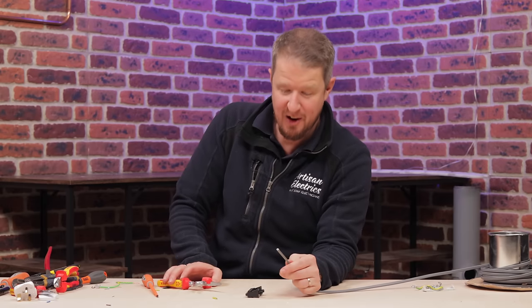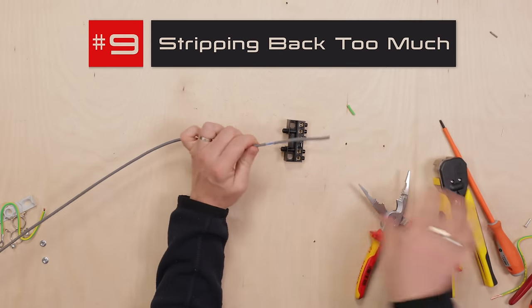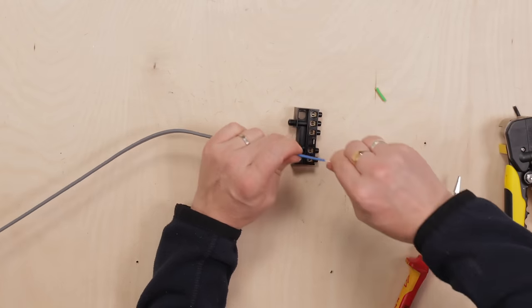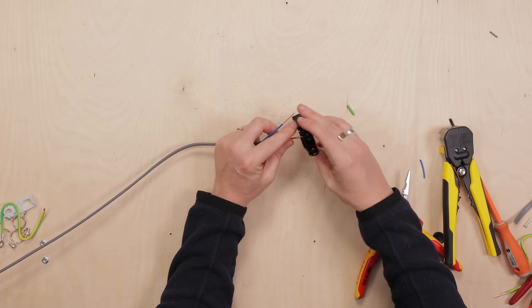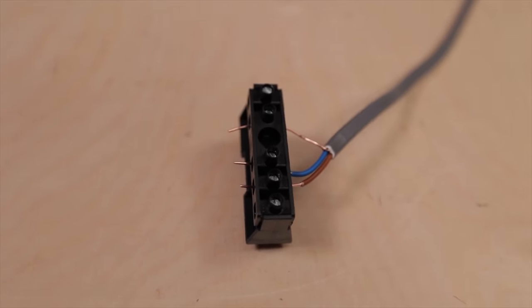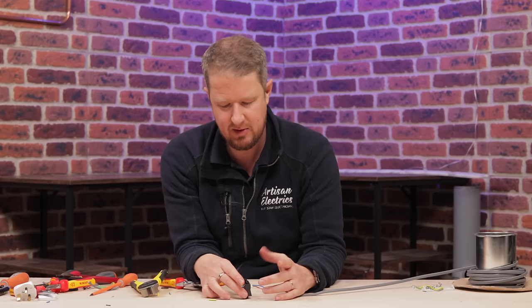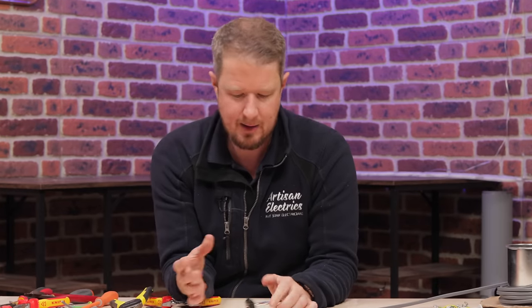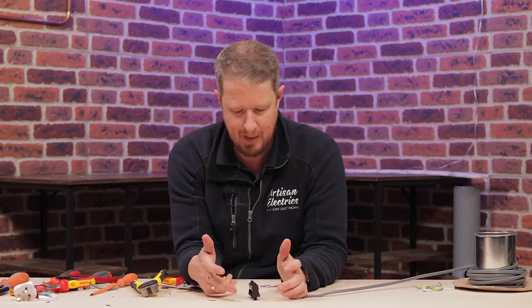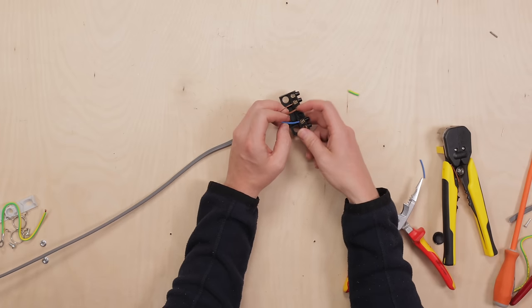Another classic DIY electrical mistake that we see a lot is people stripping the wires back too much so they strip the outer sheath like that and then they strip the bare copper like that then they bodge the wires into the terminals like so and they leave lots of bare copper. Now you might ask what's wrong with this well this is going to be enclosed in a junction box so nobody can touch these terminals right or maybe this is in the back of socket or a light fitting or something. Okay so if it's enclosed technically there's no live parts exposed it could be worse but the issue is it's just bad bad practice.